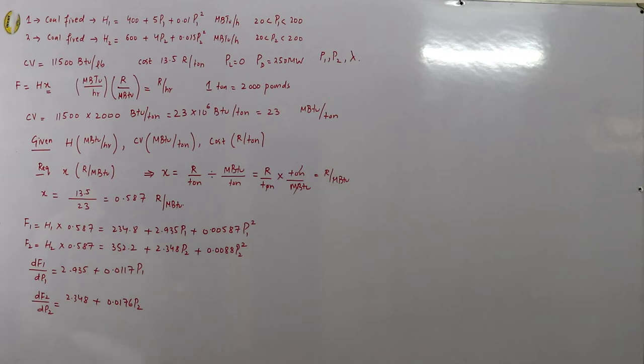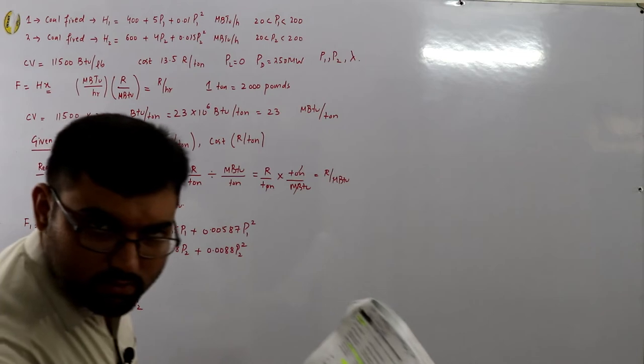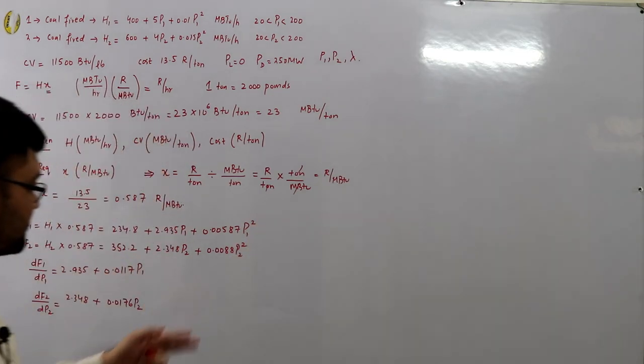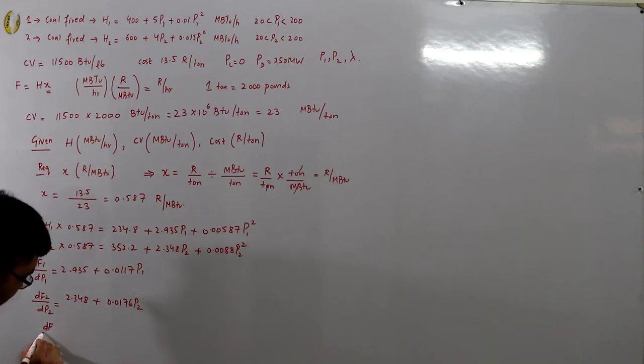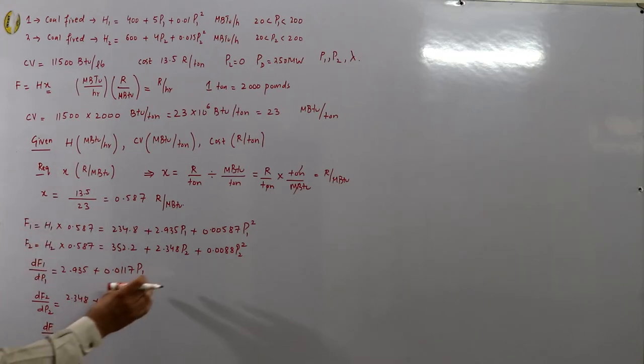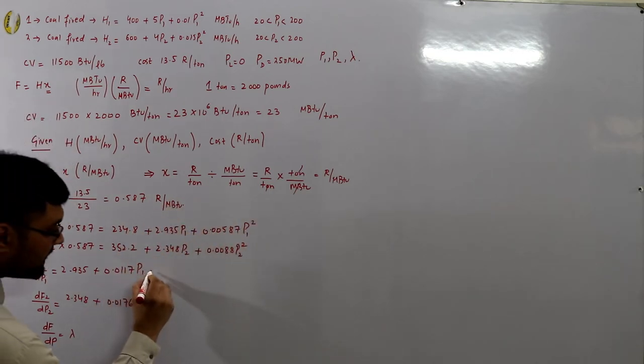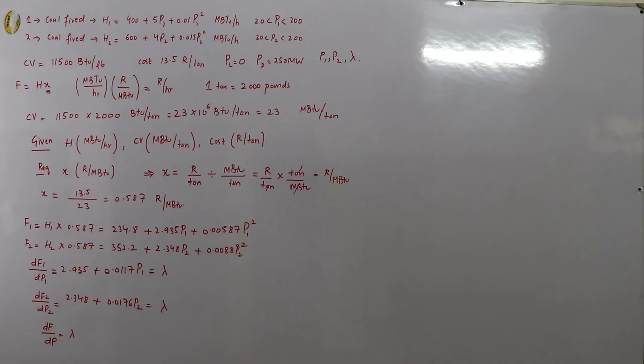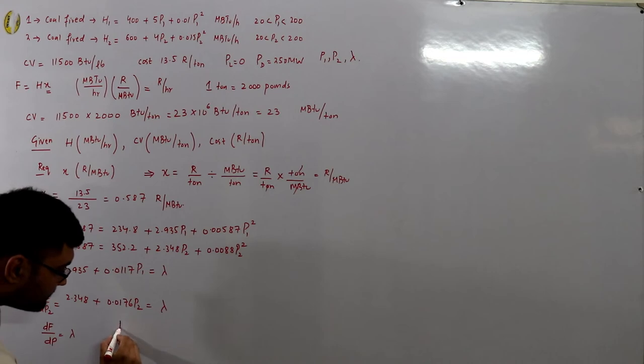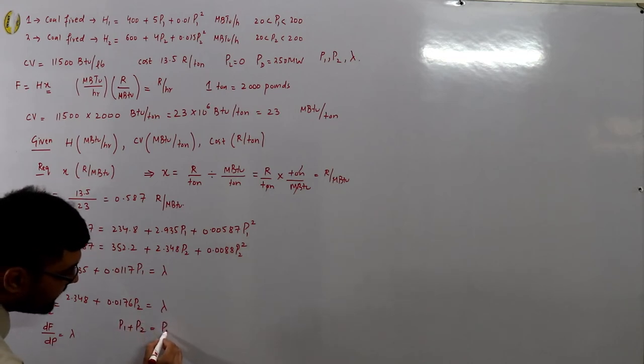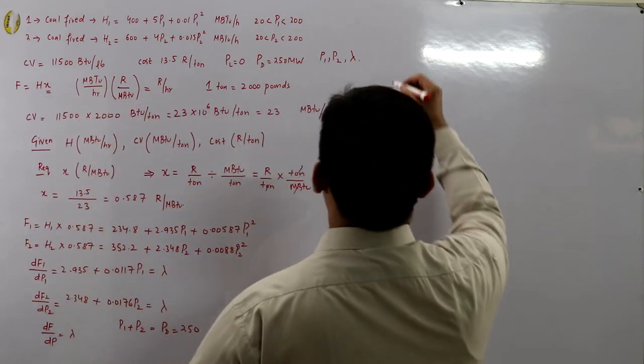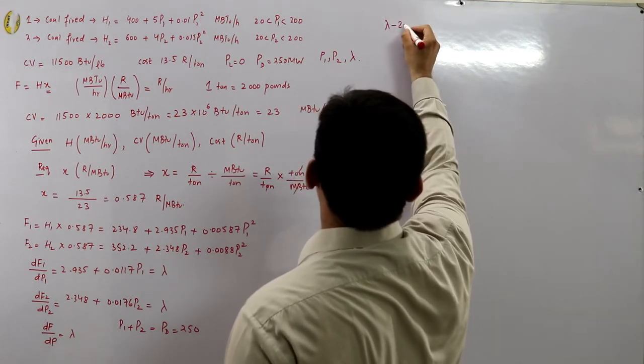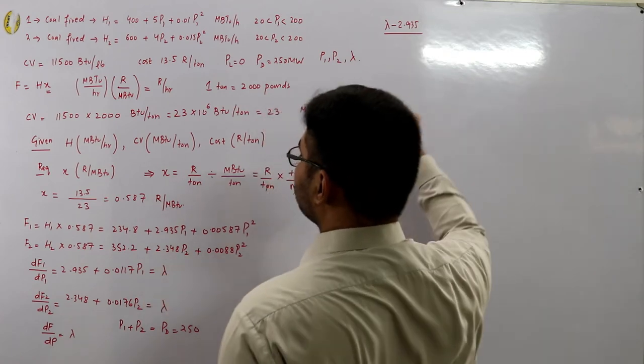We know that dF/dp = lambda. Since there are no losses, we set each incremental cost directly equal to lambda. This is a lossless system, so lambda1 = lambda2 = lambda. From the derivative equations, p1 = (lambda − 2.935) / 0.0117, and p2 = (lambda − 2.348) / 0.0176. Also, p1 + p2 = 250 MW.